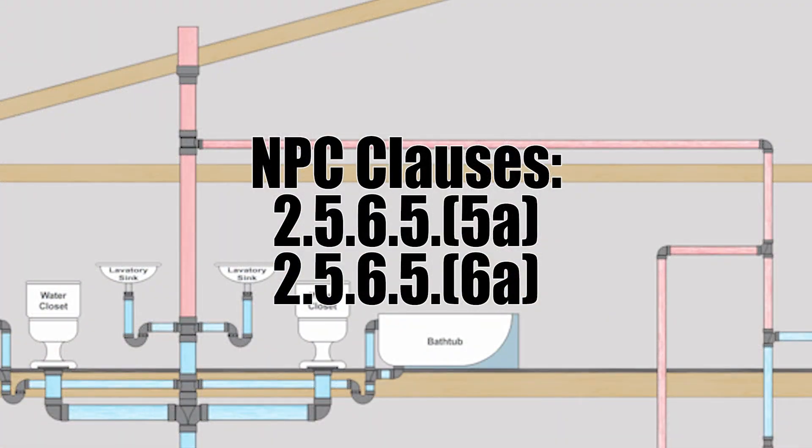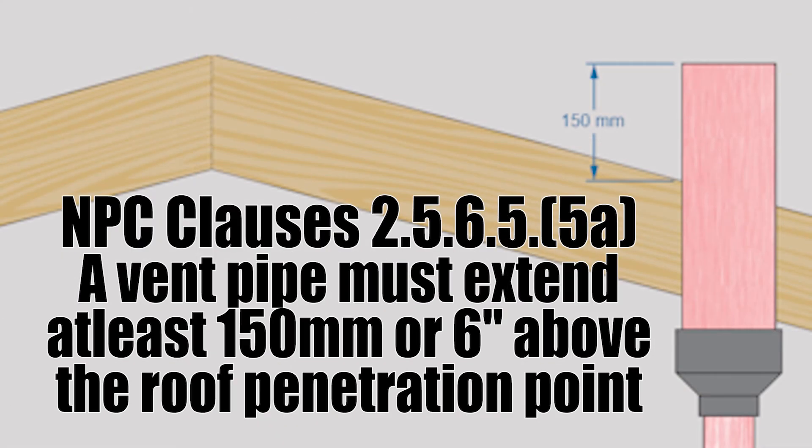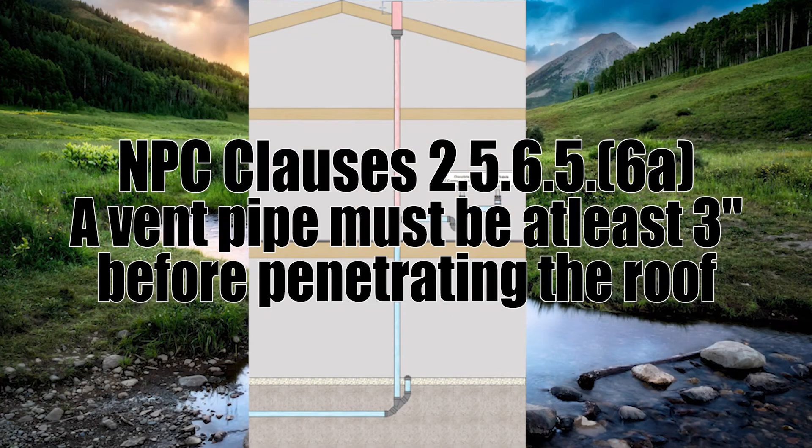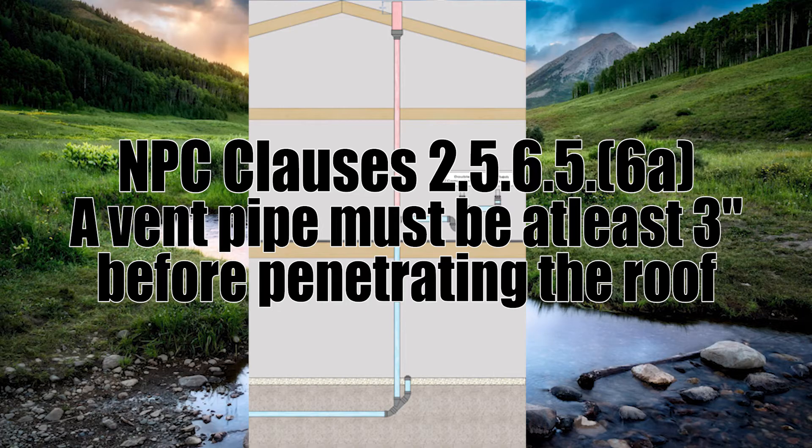None of my diagrams actually showed the roof flashing but they need to be there according to clause 2.5.6.5 5b. The last thing I want to point out comes from clauses 2.5.6.5 number 5 and 6. That vent pipe needs to extend at least 150 millimeters or about six inches above the roofline. And also if it were a different vent penetrating from something else it would need to be minimum three inches.